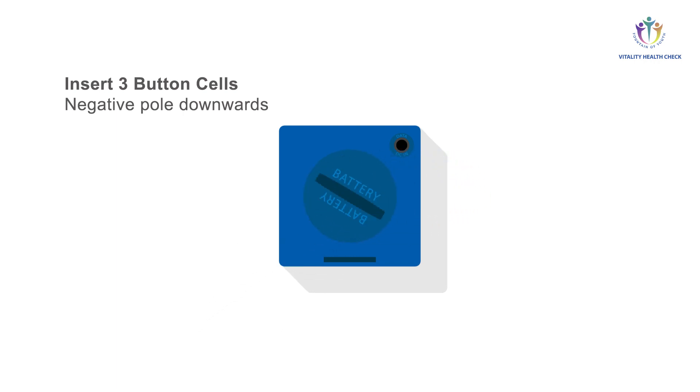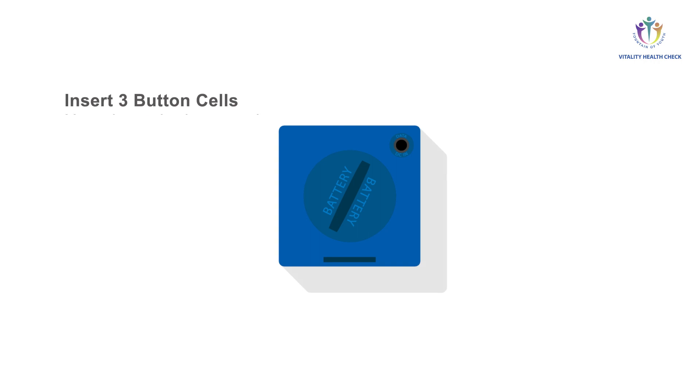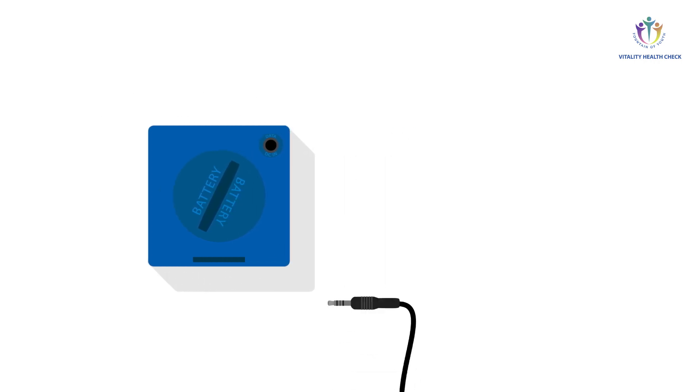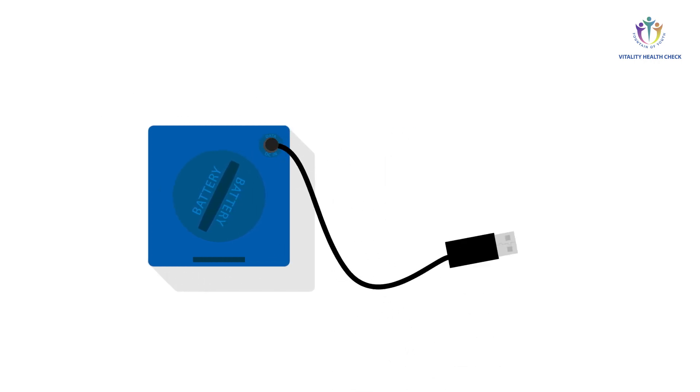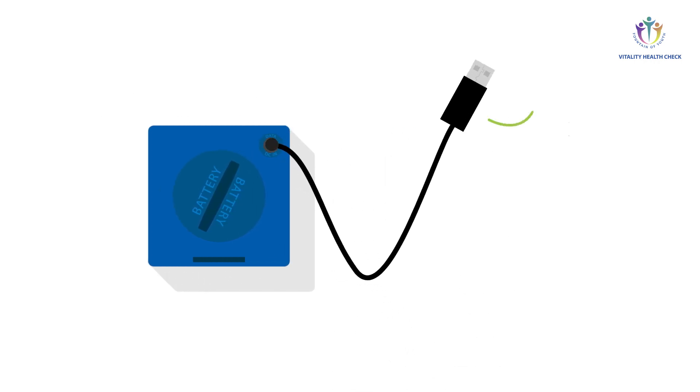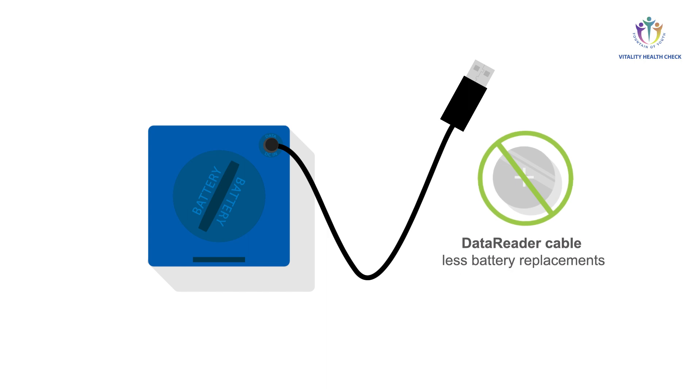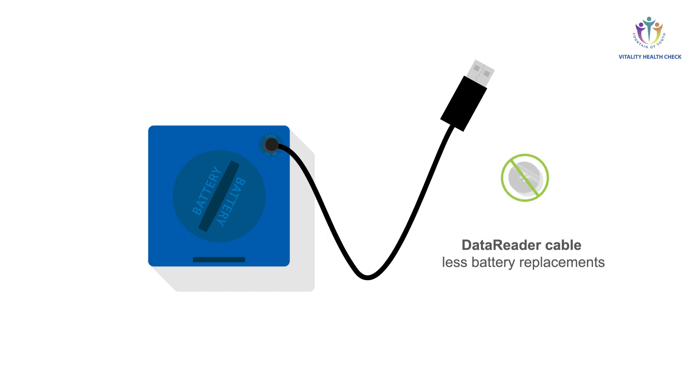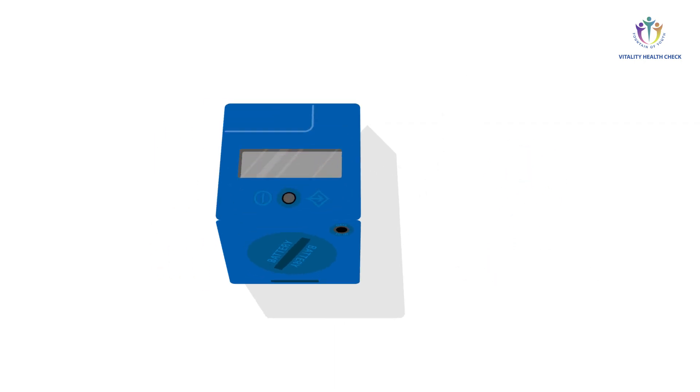You may also use the VHC reader with the optional data reader USB adapter cable to store or access data and to configure the device via a PC. The data reader cable allows you to ensure permanent power supply via USB, limiting the frequency of battery replacements. This is quite useful if you use the built-in timer of the VHC reader frequently.